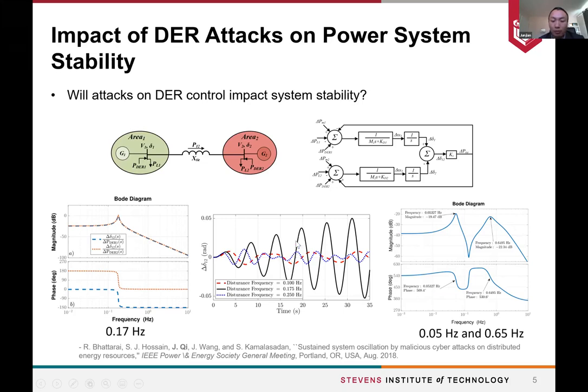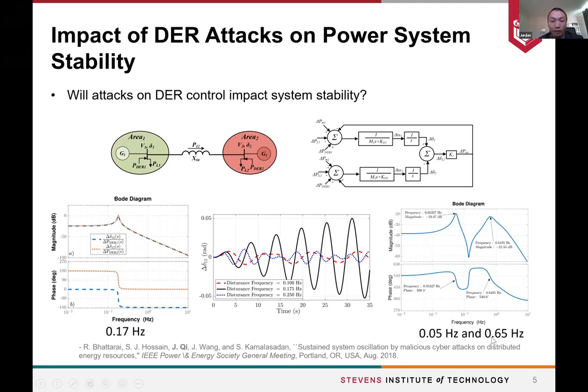This natural frequency can be validated by simulation — a disturbance at around 0.17 Hz significantly increases the magnitude of oscillation. In power systems, power system stabilizers (PSS) are designed to damp those oscillations. The PSS reduces the natural frequency peak, but also creates two lower peaks at different frequencies. For example, a low-frequency mode at about 0.05 Hz and a higher-frequency mode at about 0.65 Hz — and these two modes can be exploited by attackers to launch successful attacks impacting system stability.